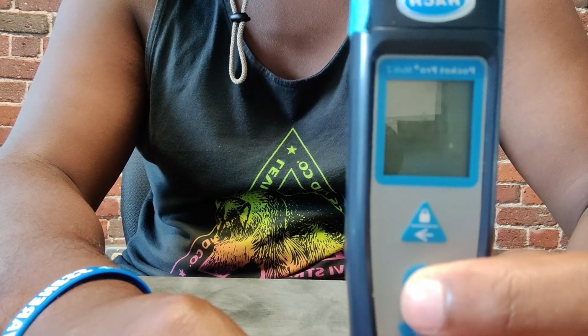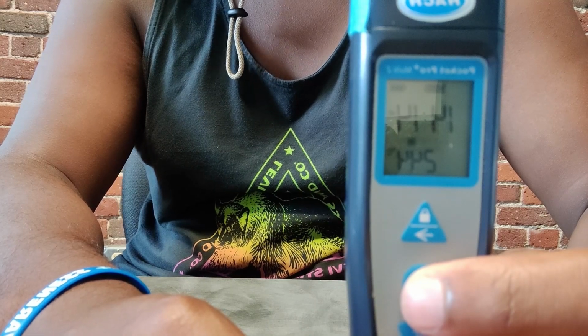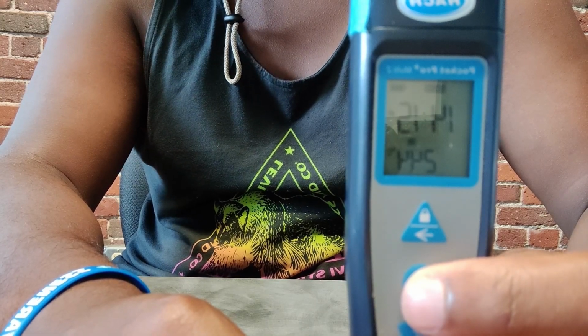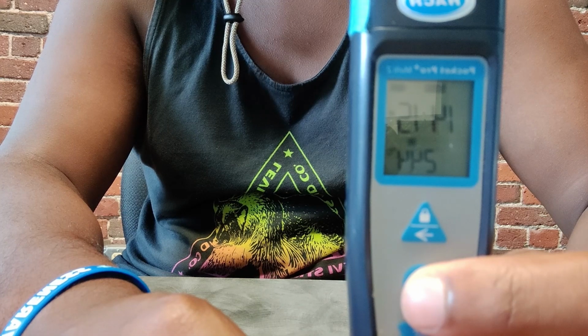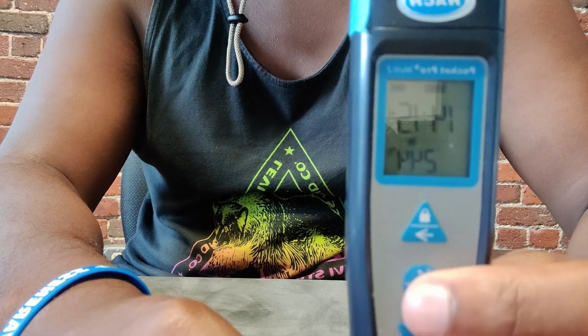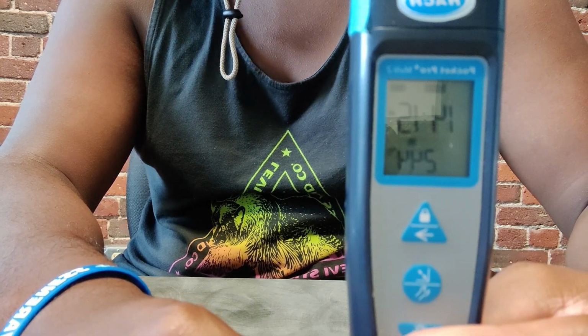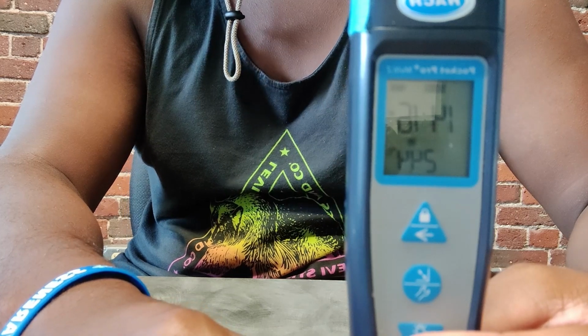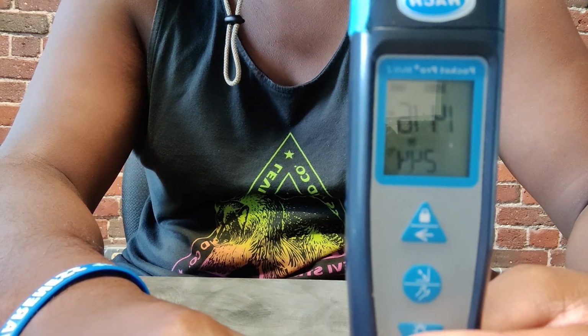And the machine will automatically flash end and return you to the normal testing screen, where the bottom row is always temperature and the top is whatever the machine is sensing from the sample. Let this number settle for 10 to 15 seconds, as before with pH, and write down whatever number you see for conductivity, remembering the unit.